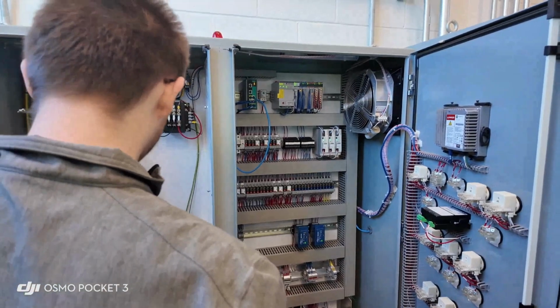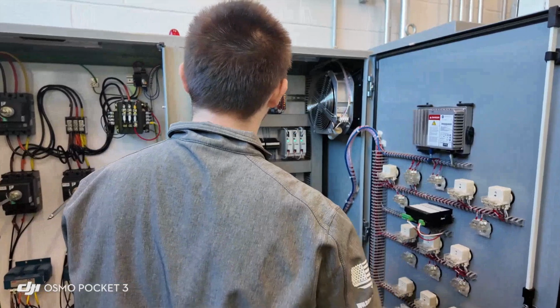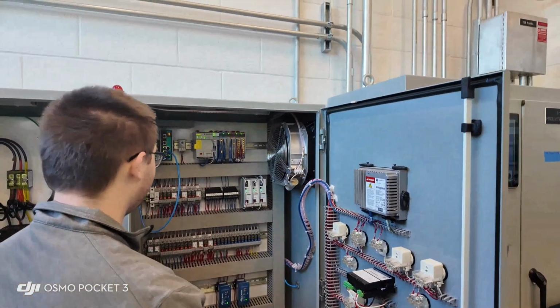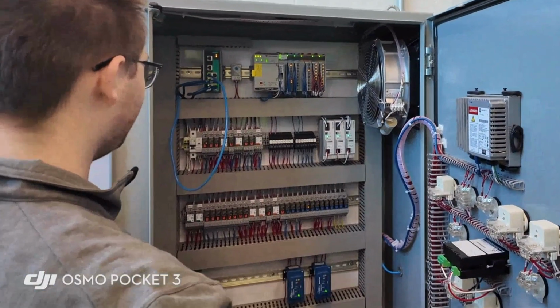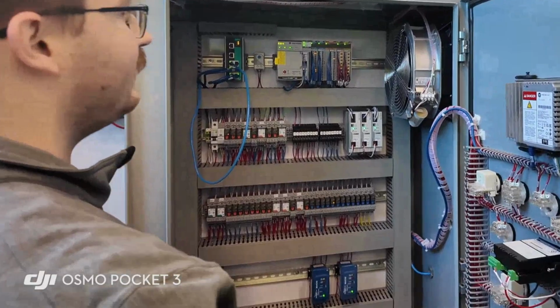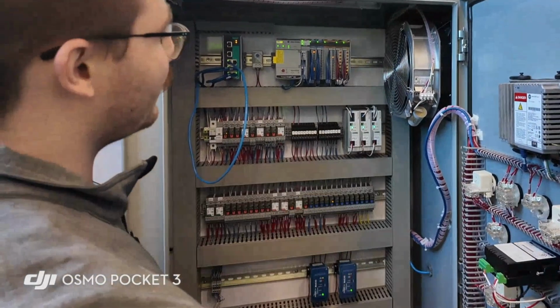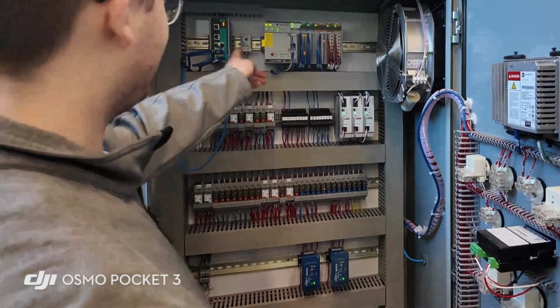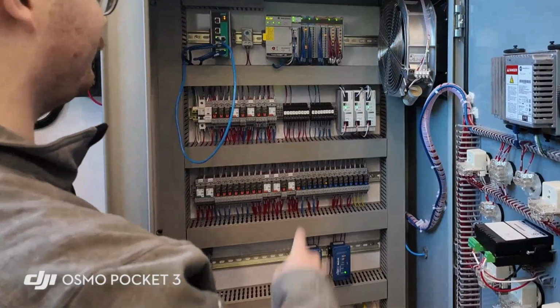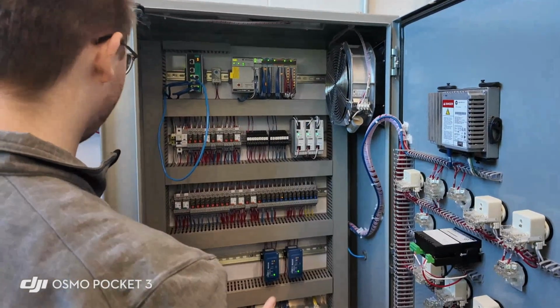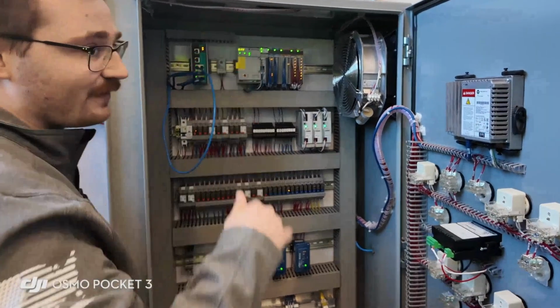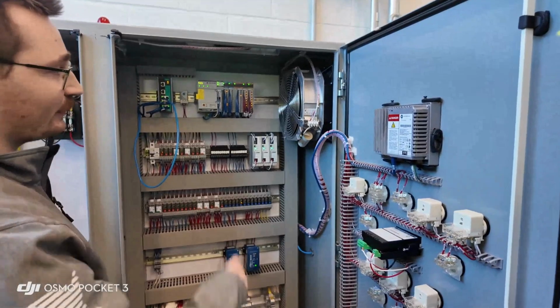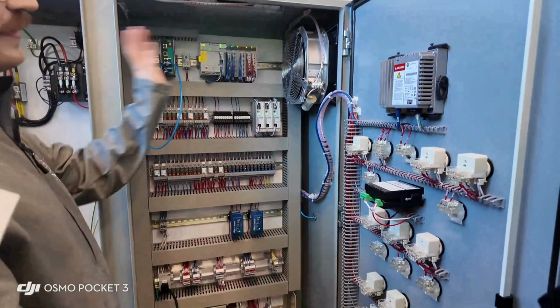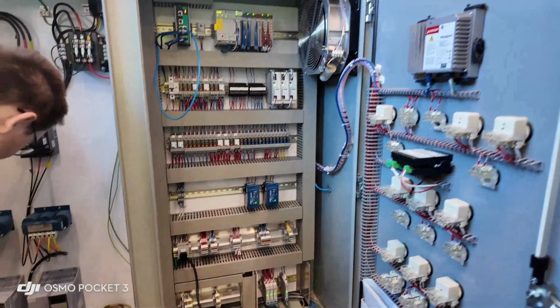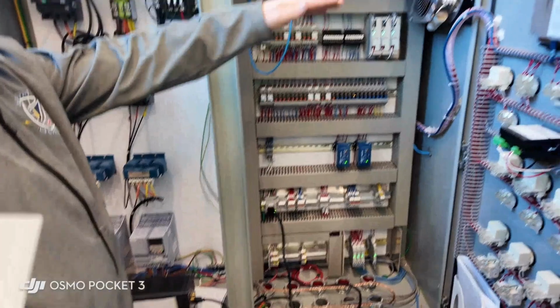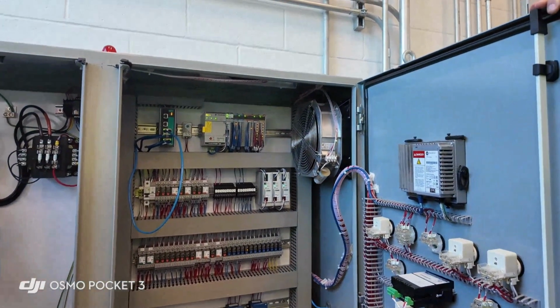Now, so this side, we'll work our way over to here. So we have an 8-port Ethernet switch, which is used for communications between Ethernet equipment inside and communicating over to this panel over here for back to SCADA. We have a temperature switch, which controls the fan. So pretty much if this panel gets over 95 degrees internally, it'll kick on the fan, and it's going to suck all the hot air out, and it has its vent on this side, so it's going to pretty much circulate through and out, and it's going to cool down the internal temperature of the panel.